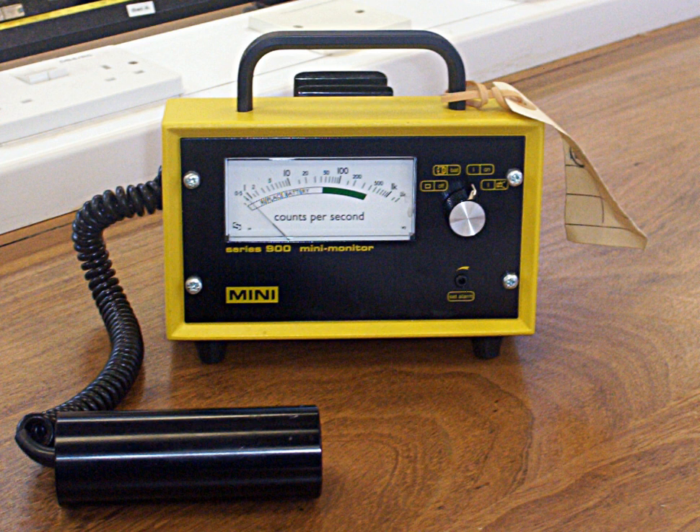Although the tube walls have a greater stopping power than a thin end-window, they still allow more energetic particles to reach the fill gas. End-window Geiger counters are still used as a general-purpose, portable, radioactive contamination measurement and detection instrument, owing to their relatively low cost, robustness, and relatively high detection efficiency, particularly with high-energy beta particles. However, for discrimination between alpha and beta particles or provision of particle energy information, scintillation counters or proportional counters should be used, as those types are manufactured with much larger detector areas.